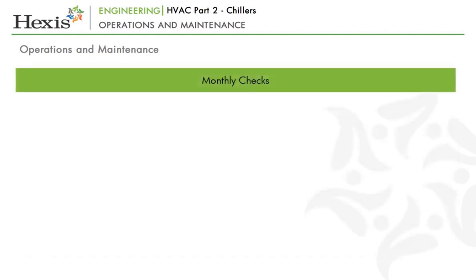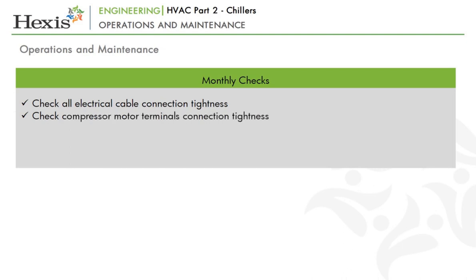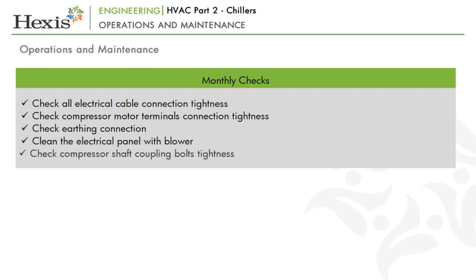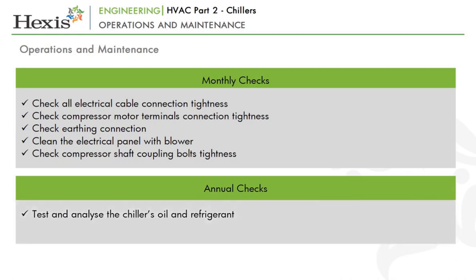Here is the list of monthly and annual checks. Monthly checks include: checking all electrical cable connection tightness; checking compressor motor terminal connection tightness; checking earthing connections; cleaning the electrical panel with a blower; and checking compressor shaft coupling bolts tightness. Annual checks include: testing and analyzing the chiller's oil and refrigerant; and conducting eddy current testing to check the chiller tubes.